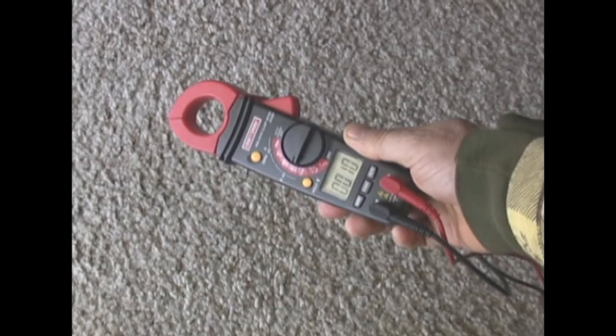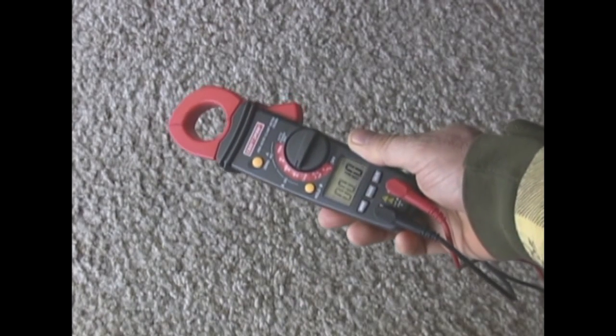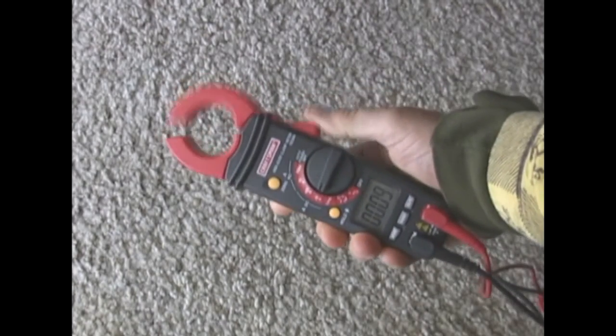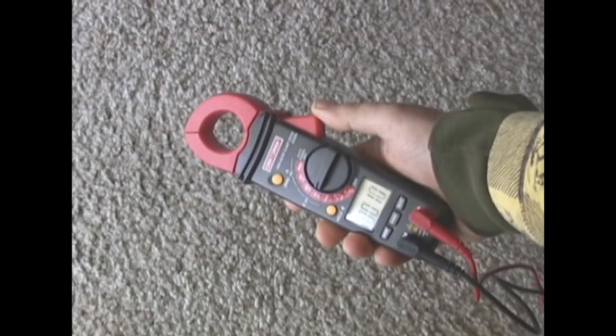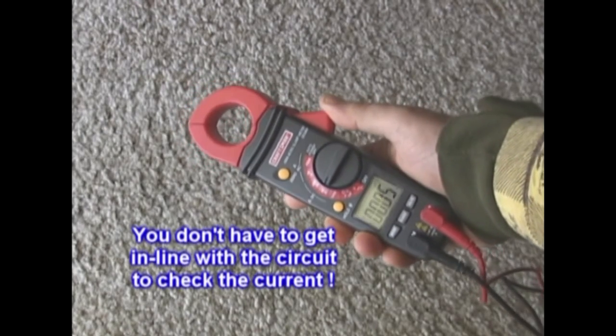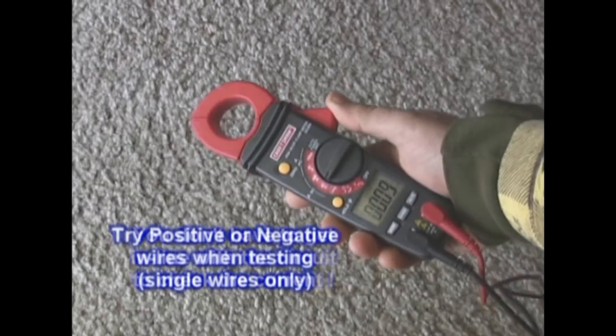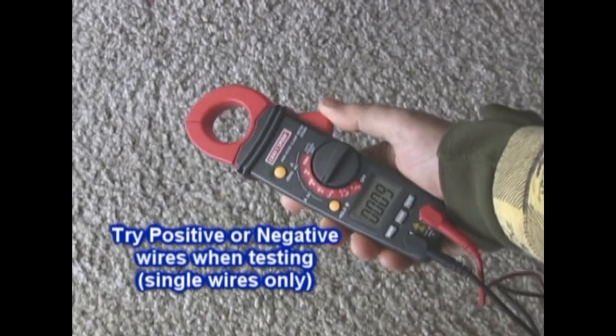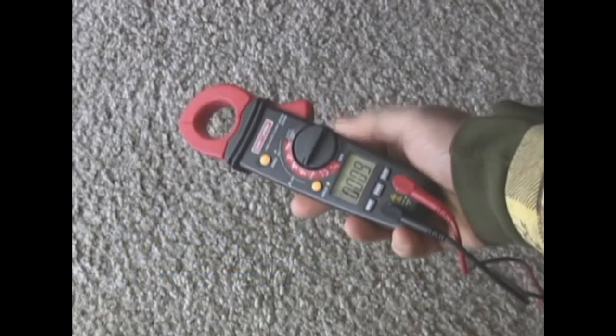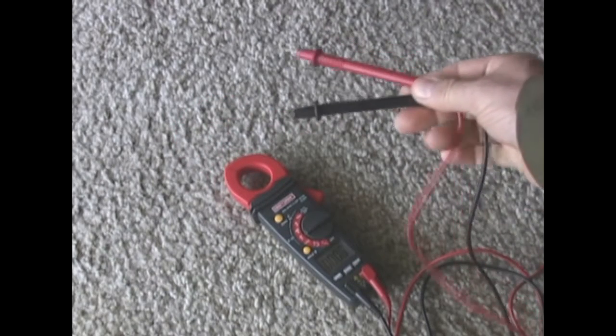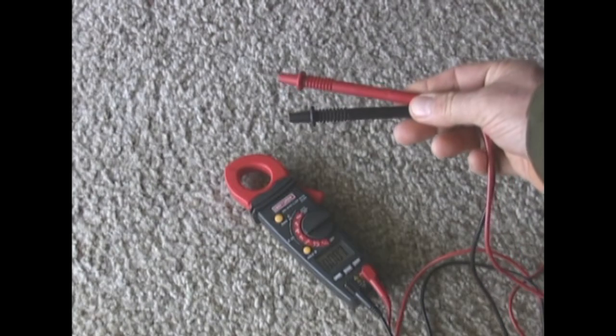This is a clamp-on type of multi-tester, really good for solar applications because it has a clamp at the top. Rather than breaking the circuit to get current readings, you can just put it around the wire, say coming down from the panels, one at a time around the red wire, and sometimes the black will work too, and it'll give you your current reading right on the LCD display. Plus, it also has the standard probes, which we showed you how to use for voltage and resistance readings.